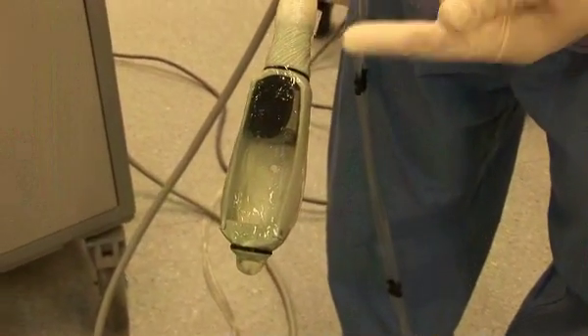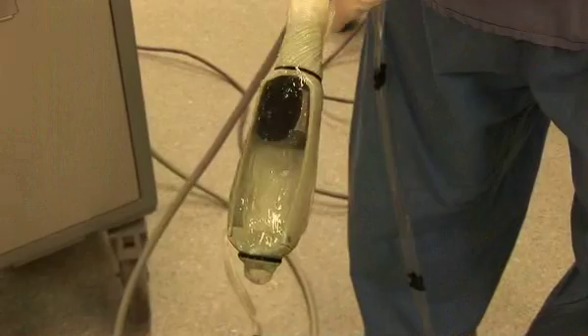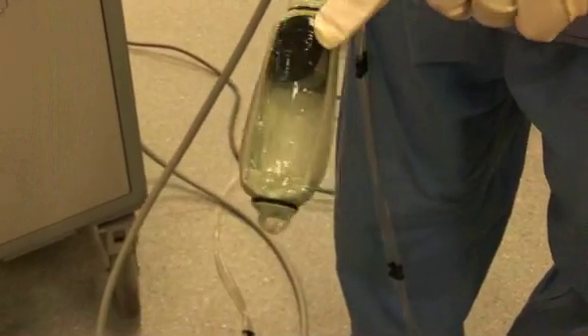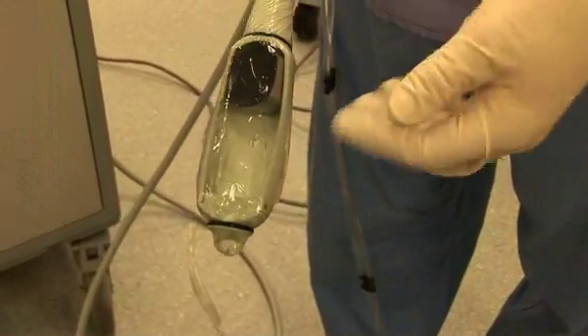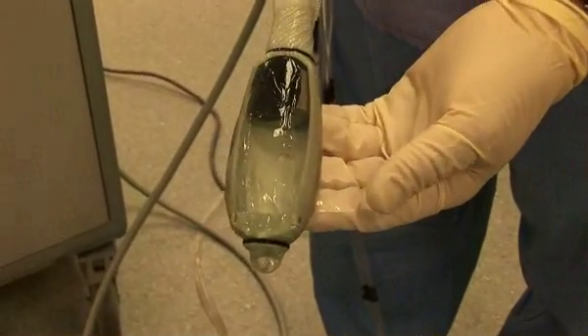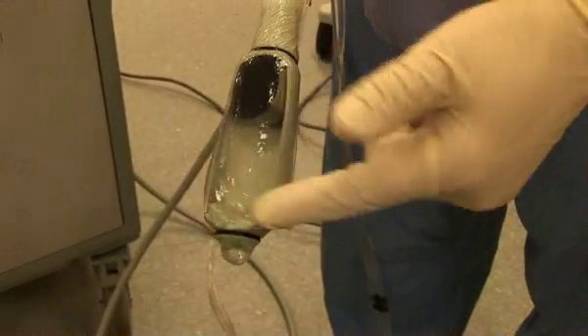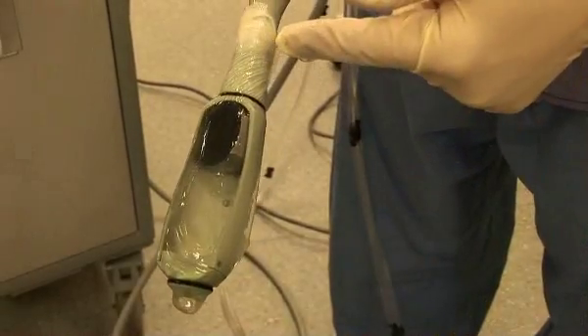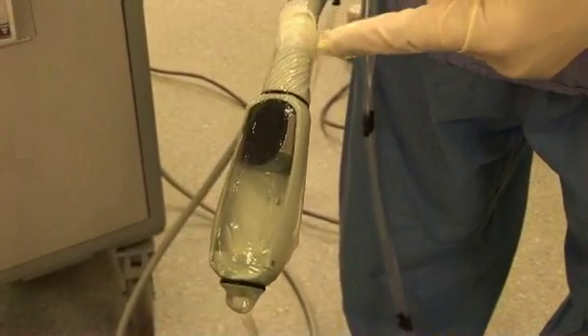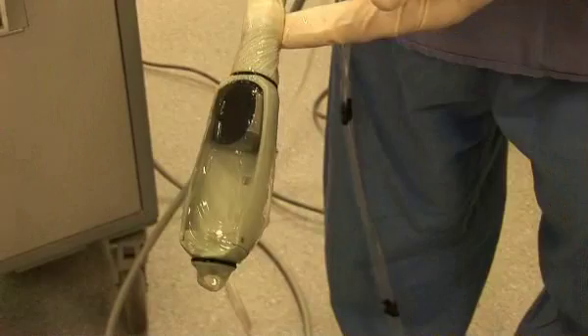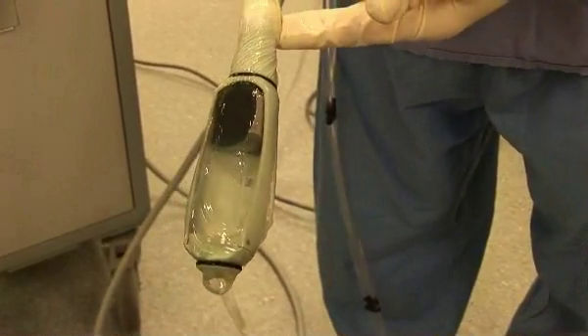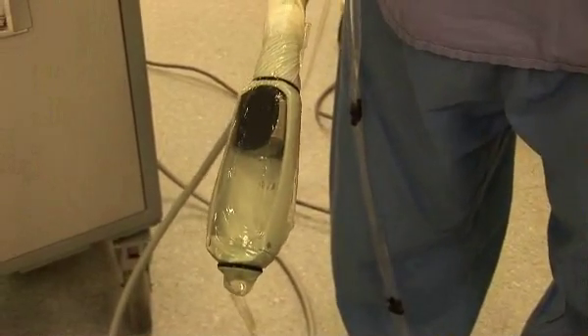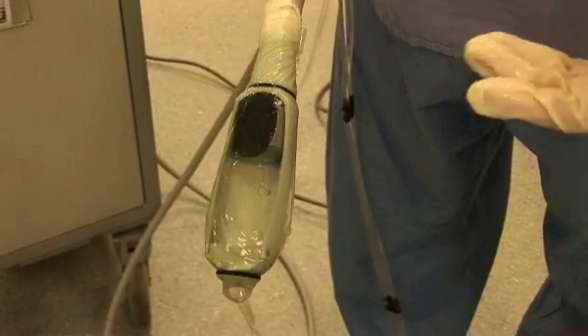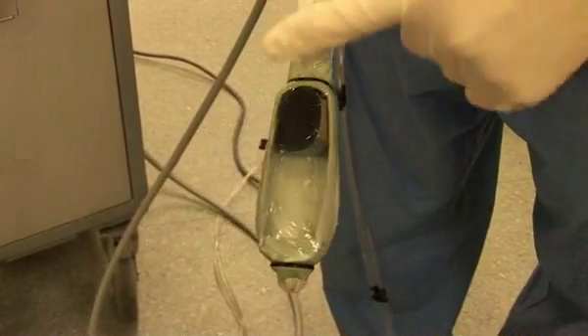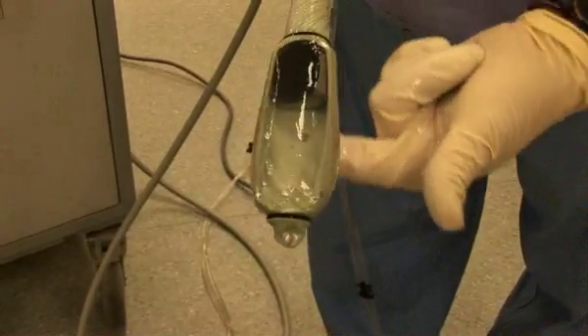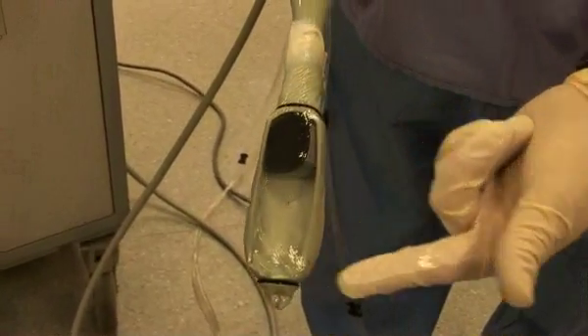Okay, this is the device which goes inside the patient. It has a transducer within the probe. The probe is covered with a condom. The condom is filled with degassed water which circulates through the system throughout the treatment, keeping the temperature down to 17 degrees centigrade. And that's to assist with rectal cooling and probe cooling. So it serves two purposes. The gel you see on the outside is to aid contact with the rectal wall.